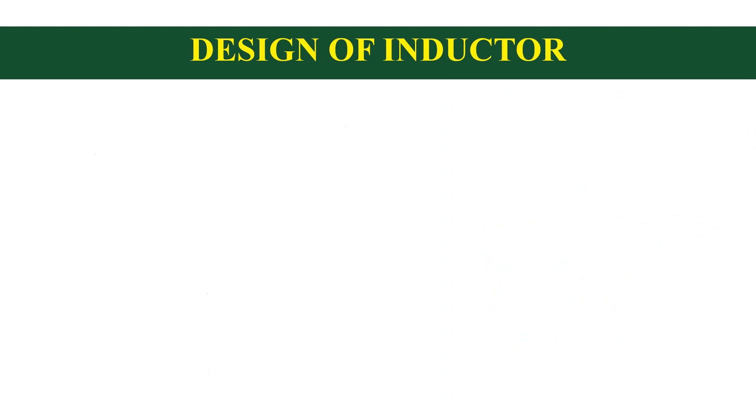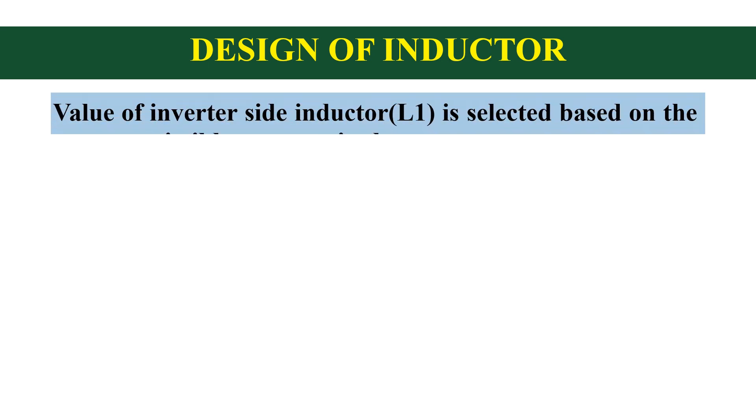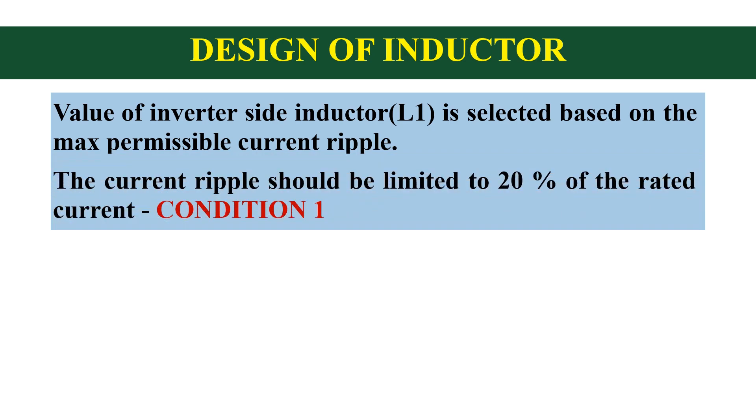Now we will look at the design of inductor. The design of inductor is based on two conditions. Value of inverter side inductor is selected based on the max permissible ripple current. As a thumb rule, current ripple should be limited to 20% of the rated current, and that is the first condition.